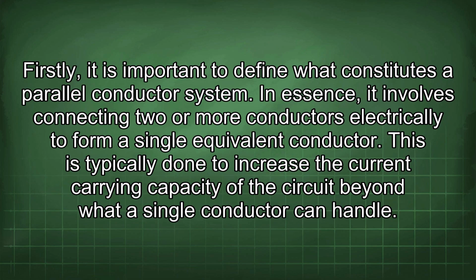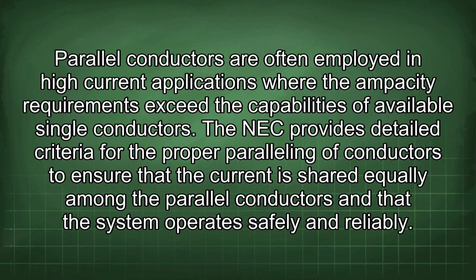Firstly, it is important to define what constitutes a parallel conductor system. In essence, it involves connecting two or more conductors electrically to form a single equivalent conductor. This is typically done to increase the current carrying capacity of the circuit beyond what a single conductor can handle. Parallel conductors are often employed in high current applications where the ampacity requirements exceed the capabilities of available single conductors.